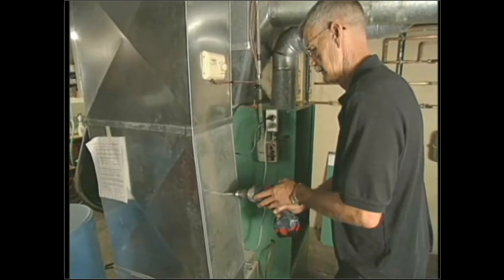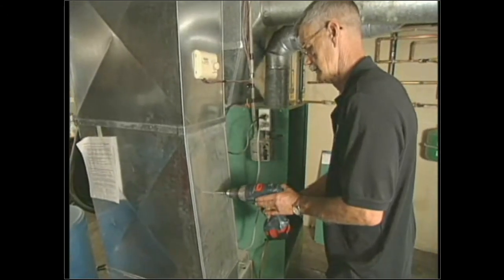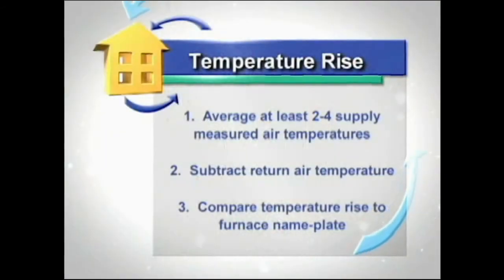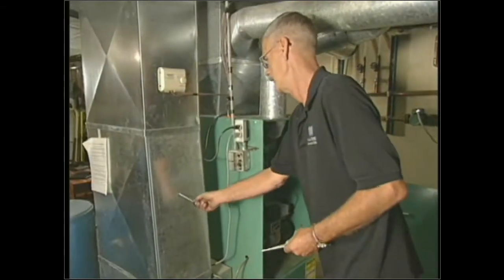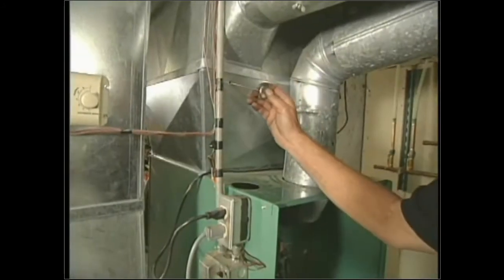We put another hole midway between the shoe and the return, right in the middle of the drop, and that gives us our return temperature. After steady state, you take the readings, add all 4 of them together, divide by how many test points you have, and then subtract the return air temperature, because you're trying to find the difference between the air coming from the house and the air that's coming from the furnace.